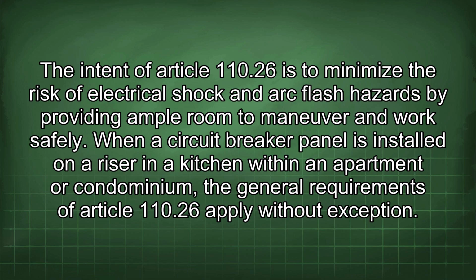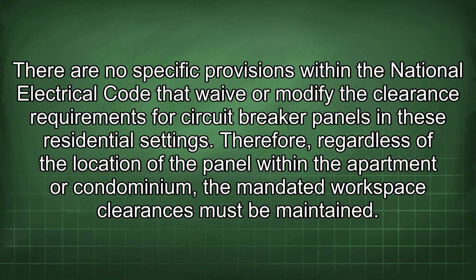When a circuit breaker panel is installed on a riser in a kitchen within an apartment or condominium, the general requirements of Article 110.26 apply without exception. There are no specific provisions within the National Electrical Code that waive or modify the clearance requirements for circuit breaker panels in these residential settings. Therefore, regardless of the location of the panel within the apartment or condominium, the mandated workspace clearances must be maintained.